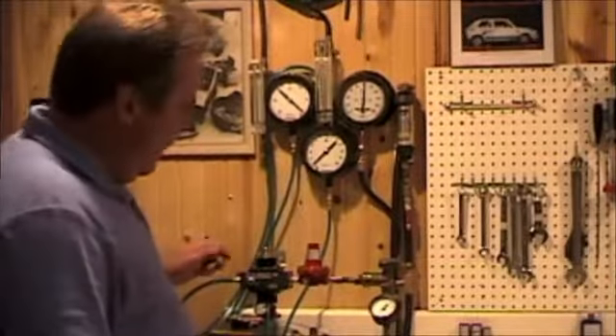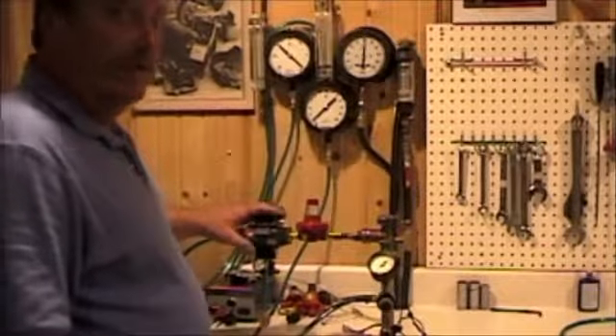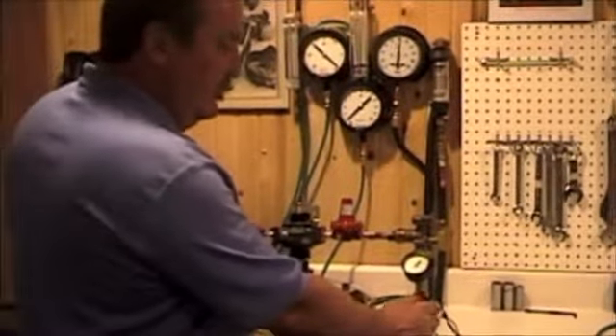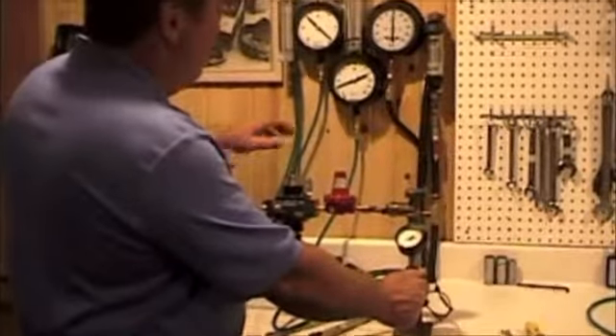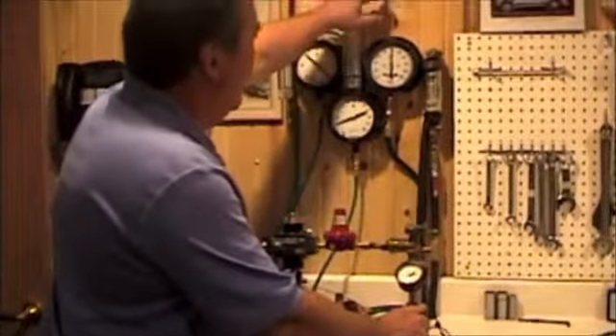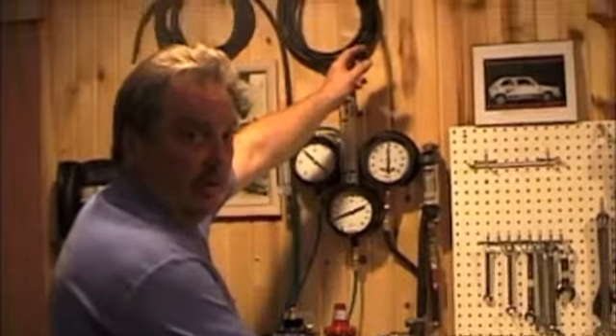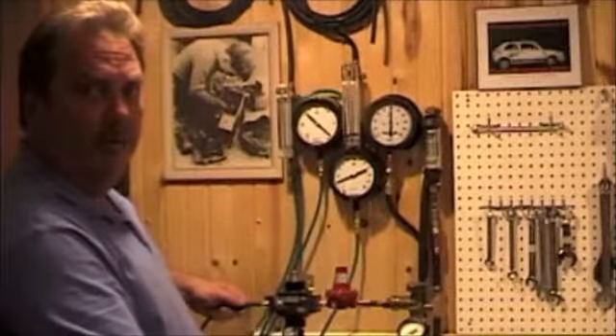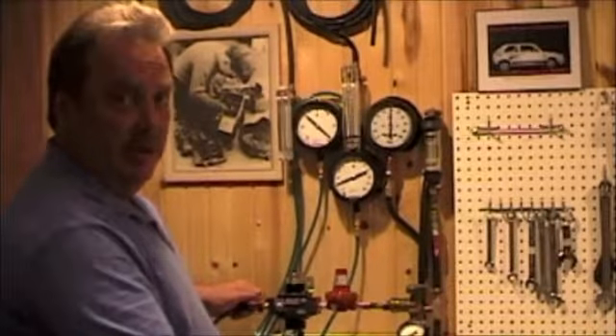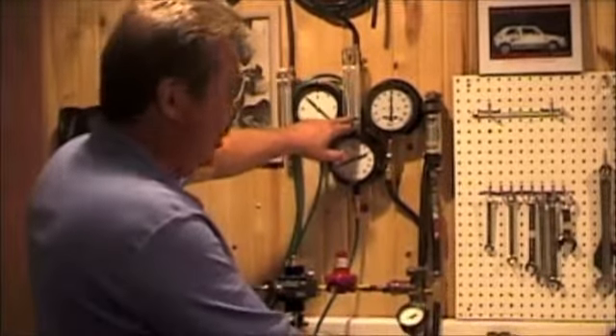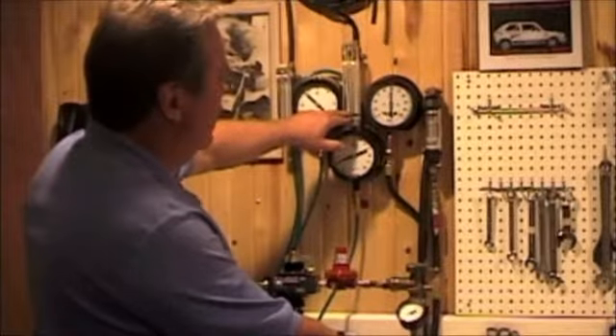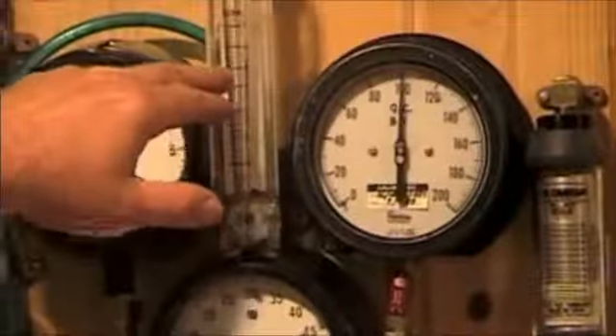Okay, we're back. We have set a 5-pound start time on this unit, and we know that as we bring up the pressure, you see 5 pounds. You can come back here, and this is where the hose exits. You can feel it's starting to flow. That was the reason we left the calibrator off of it for setting start time, so it's very easy to tell when it's flowing propane. We're just starting to lift. There's a little weight in here that shows how much propane will be flowing for how much pressure. Hopefully you can see this, but as I increase the pressure, I'm increasing the volume of propane being delivered.